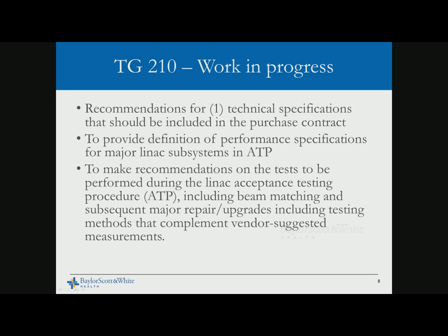TG210 is a work in progress. The goal is to recommend the technical specification that should be included in the purchase contract — physicists sometimes don't get involved at that stage, yet this is the contractual obligation. It also aims to provide a definition of performance specifications for major LINAC components, and make recommendations on tests that should be performed during acceptance testing, including both what the vendor provides and what we should verify before signing off.